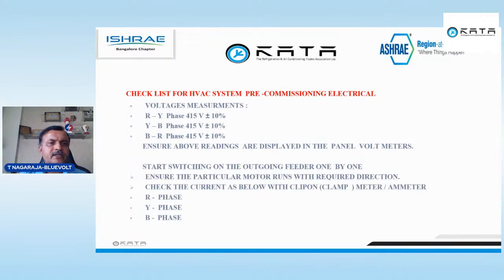Then the checklist for voltage measurement. R to Y, what will be the voltage, Y to B, then B to R. Please ensure the above readings are displayed in your meters, whether a voltmeter, multimeter or clamp meter. Start switching on the outgoing feeders one by one. Ensure the particular motor runs in the required direction. Check the current as below with a clip-on meter or ammeter, R phase, Y phase.